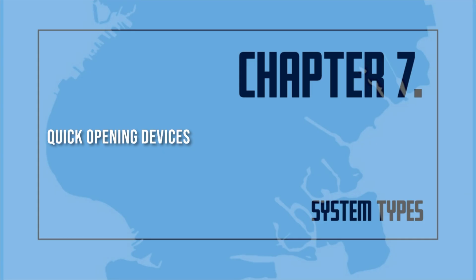They are both automatically activated when a drop of 2 pounds per square inch in air pressure is detected in the system. They quickly change the water and air pressure balance in the system. This change trips the dry pipe valve, allowing the water to force its way through the sprinkler piping in less time. The failure of an accelerator or exhauster to operate will increase the normal tripping time of a dry pipe valve.